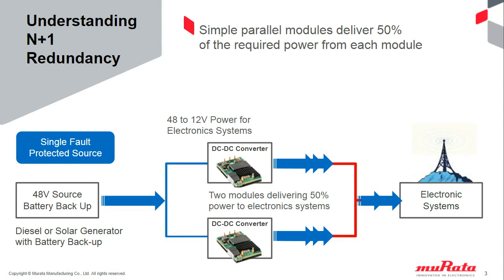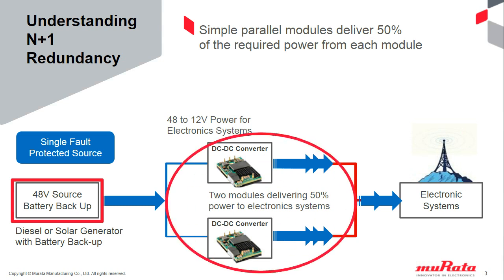So here is a simple diagram of a system that has an N+1 source. Most networking and telecom sources are N+1 because if the main system fails, whether it be an AC supply or, in this application of a remote radio head, a diesel or a solar generator is generating the power for this system. So the front end of this system is N+1 reliable. In this particular diagram, we have two modules running in parallel. Each one of these modules is delivering 50% of the power to the electronic system. And this is a high reliability system.